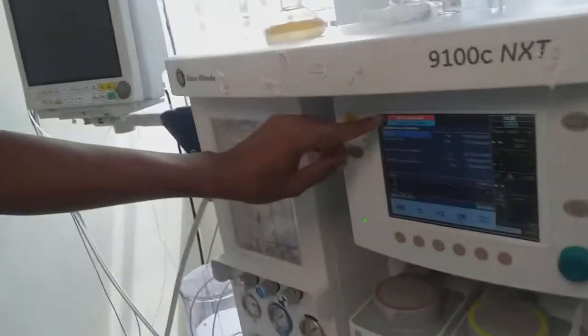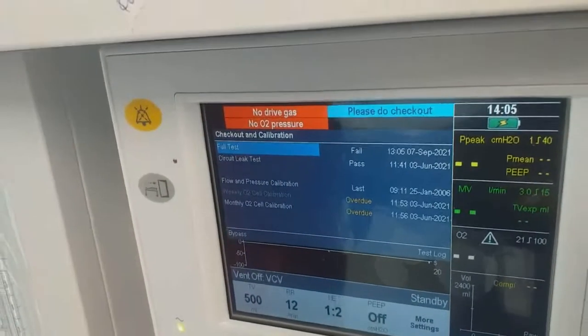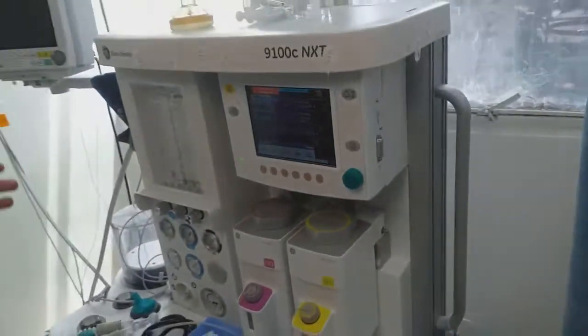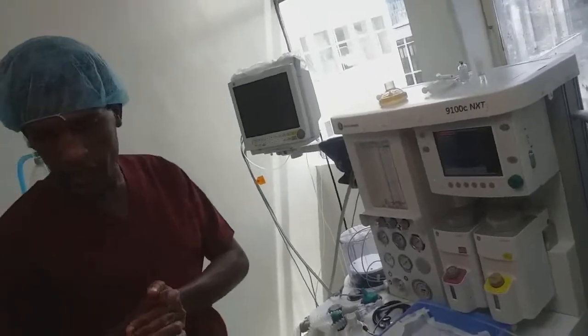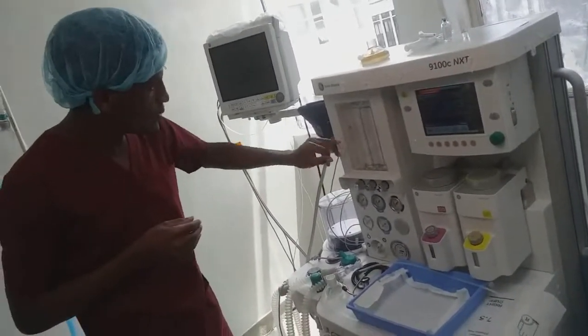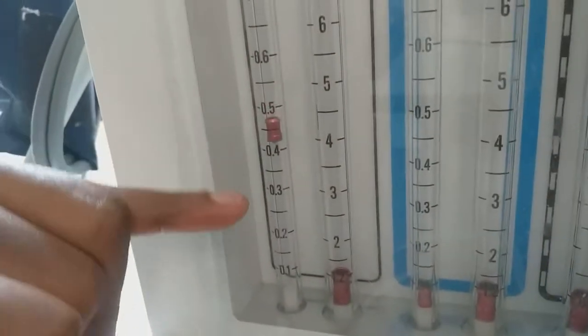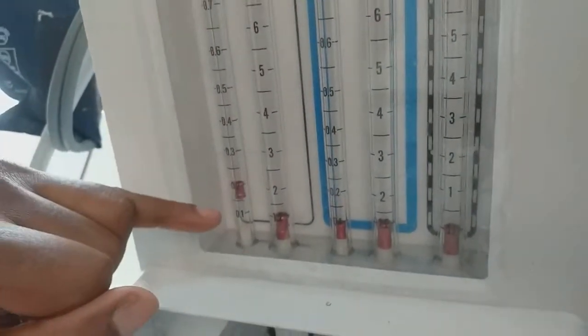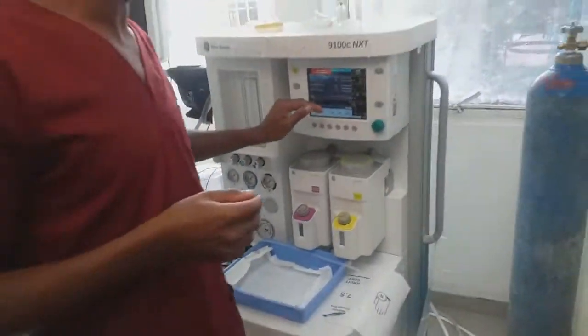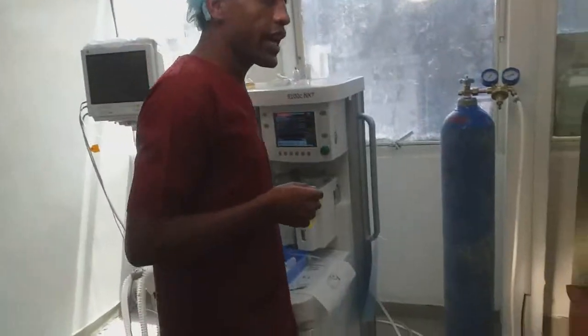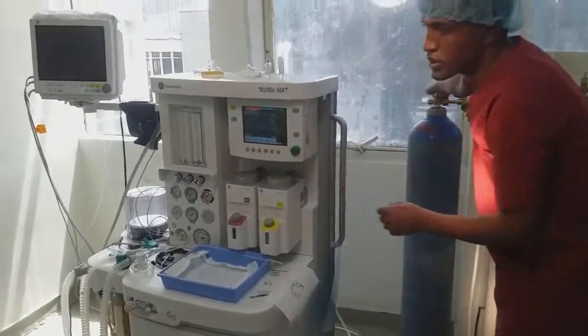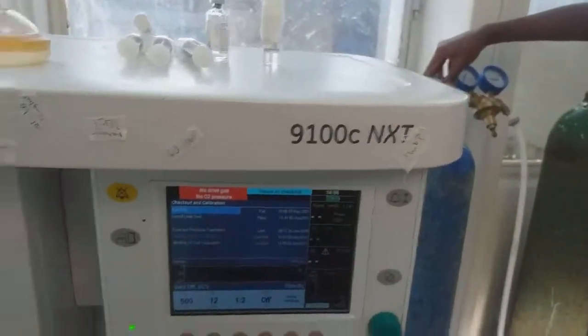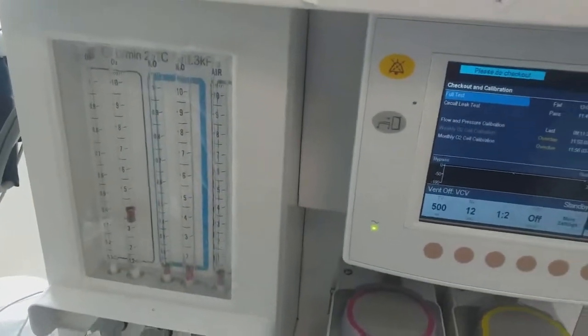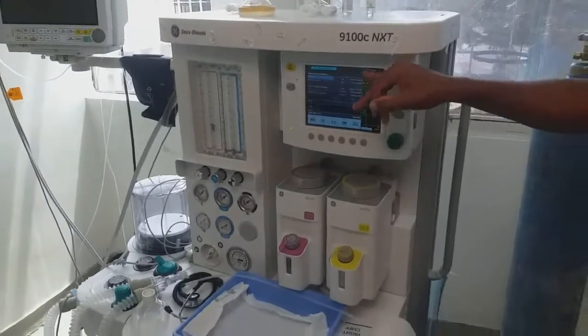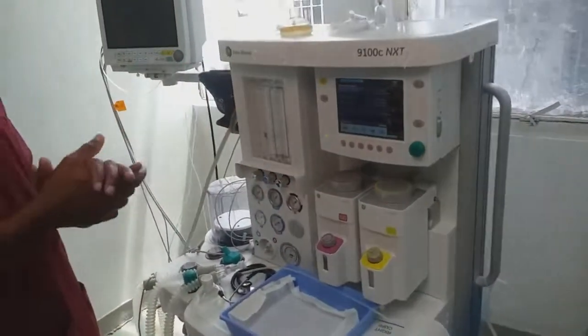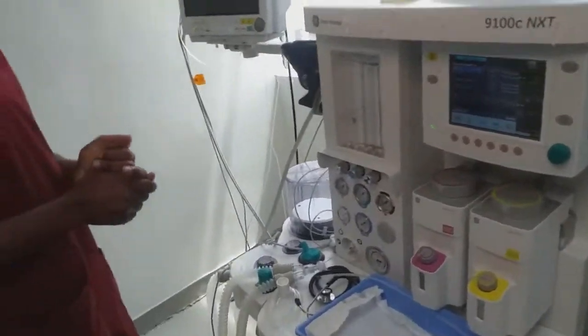Here, the alarm is starting to sound. This indicates that there is an alarm on this anesthesia machine, the best way to prevent disaster, the catastrophic event that can occur when we do anesthesia. Here, the bobbins are falling down. This indicates that the oxygen pressure alarm is functional. When I open this oxygen cylinder, this alarm should be absent. Now I am going to open it slowly. Slowly I am going to open this. Okay. Now the oxygen pressure alarm is absent.